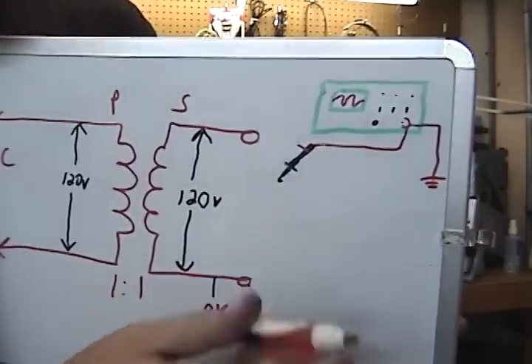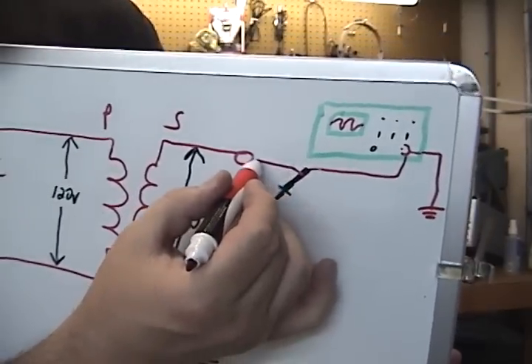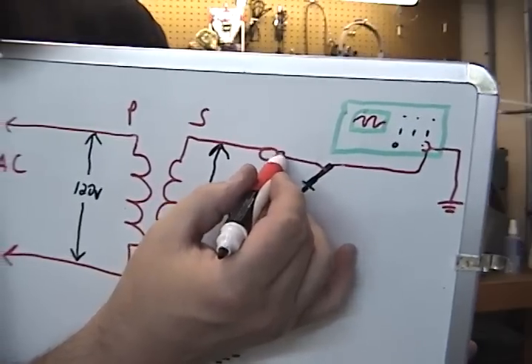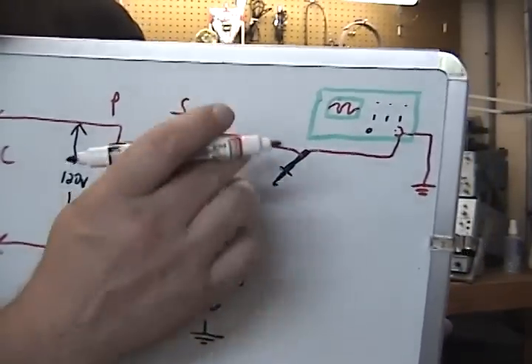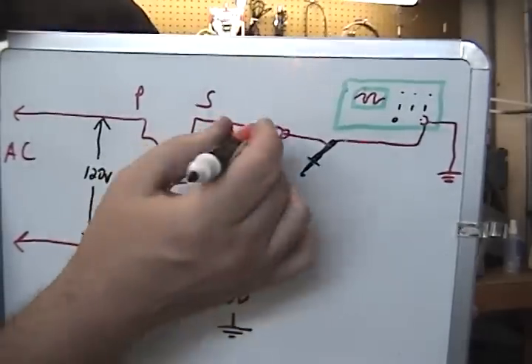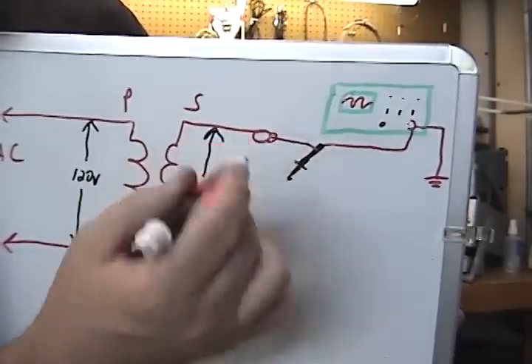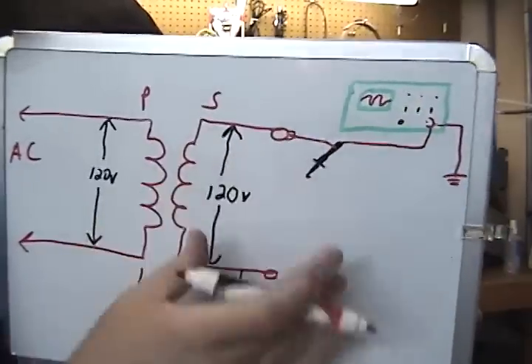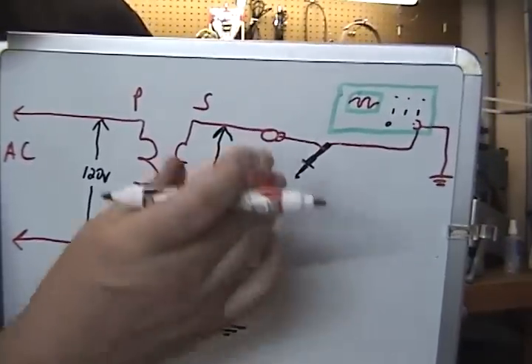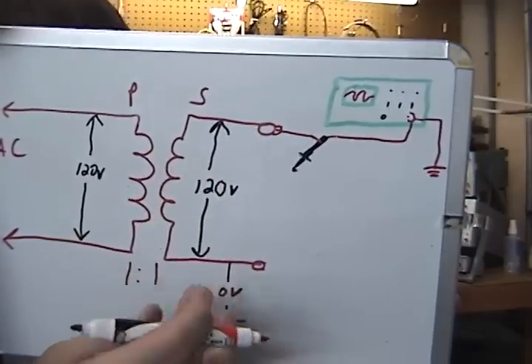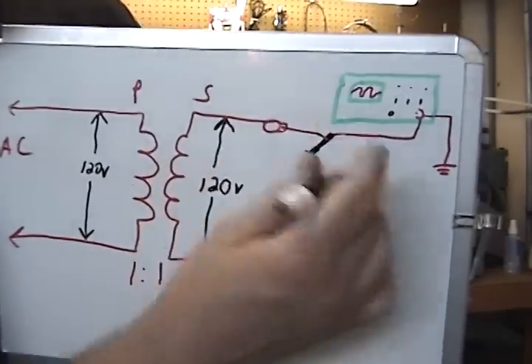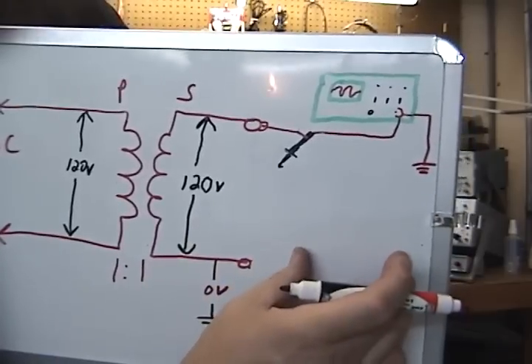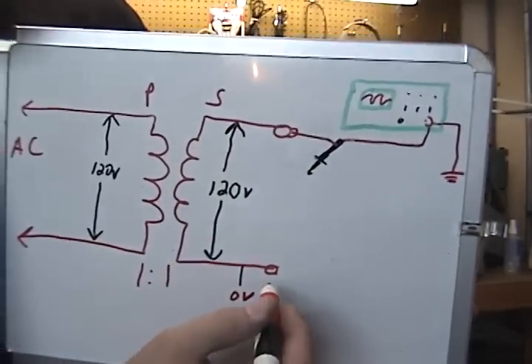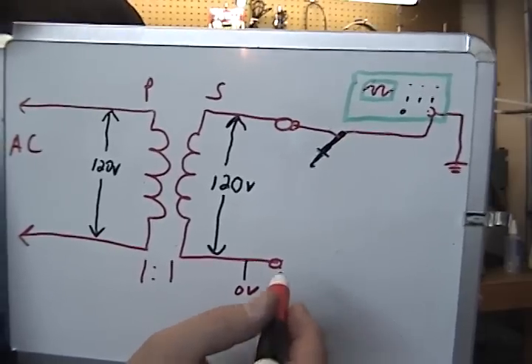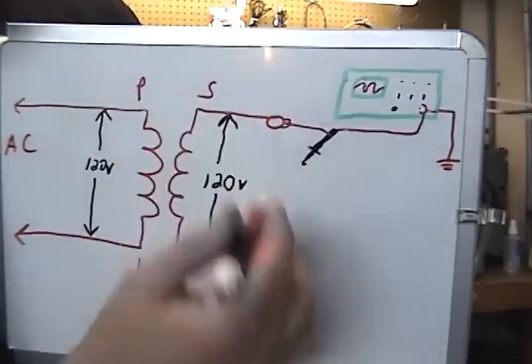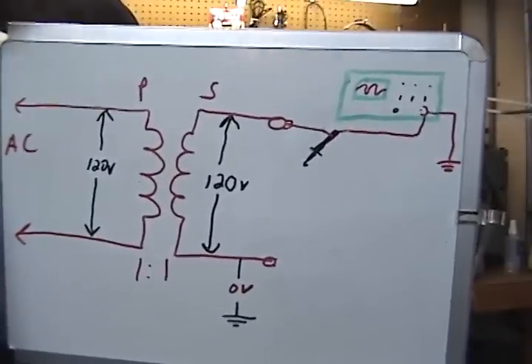Once you hook up that BNC's ground shield to any part of that circuit—in this case I went high, I could have gone low, it doesn't really matter—as soon as you do that, that becomes your new neutral, or ground reference, for your secondary and primary on the isolation transformer. Any point on your circuit under test that's hooked up to the opposite side, or any higher side voltage, is now set up as a high potential voltage environment.